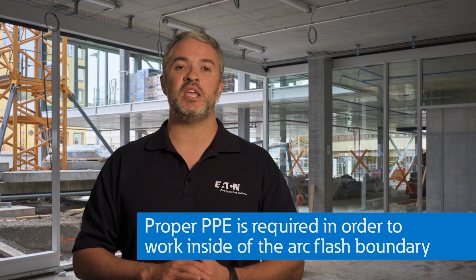As a contractor working on or around this equipment, you may find that arc flash labels are not available and you must determine how to approach the situation. This includes determining what type of PPE to wear and if you are even able to work on the equipment based on the risk associated with the level of the incident energy. For example, working on anything over 40 calories per centimeter squared is not allowed by the standards. They call that a non-labeled environment, and that's why the tables exist.